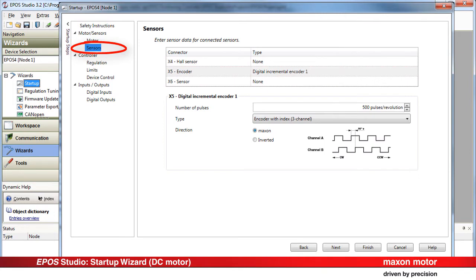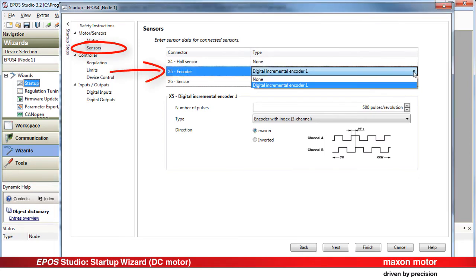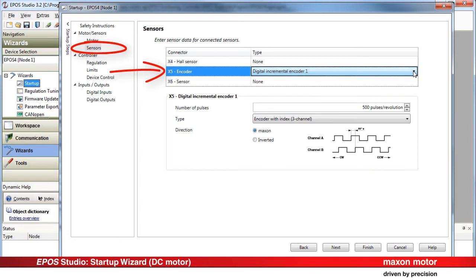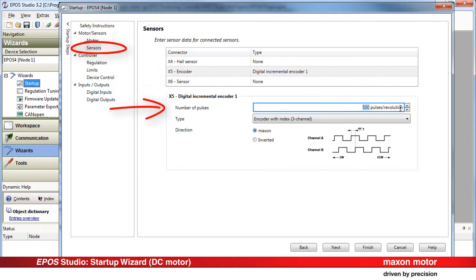Enter the sensor data for the connected sensors. Select Digital Incremental Encoder 1, a sensor type that is plugged onto connector X5 on the EPOS 4 device. Enter the encoder resolution in counts per turn. Next.